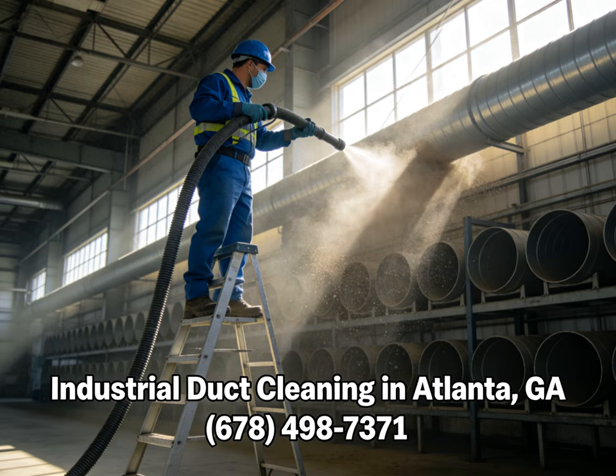Okay, wait, I'm stuck on this negative pressure idea, though. If you're turning the entire duct system into a giant vacuum, aren't you just sucking all that caked-on Georgia humidity, heavy lint, and industrial grime straight into the negative air machine? Oh, yes. Wouldn't that instantly clog the very machine trying to do the cleaning? That is a crucial logistical challenge, and it's exactly where the engineering of these machines comes into play. Because they don't just pull air into a single filter. No, these negative air machines utilize multi-stage filtration systems.